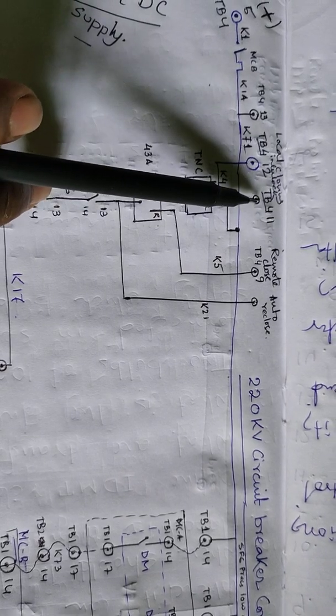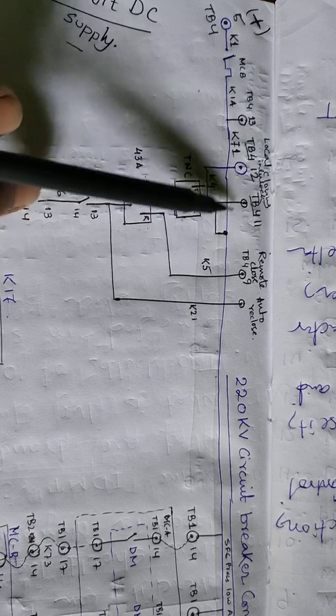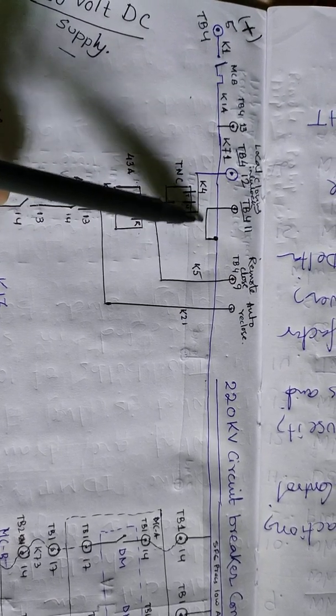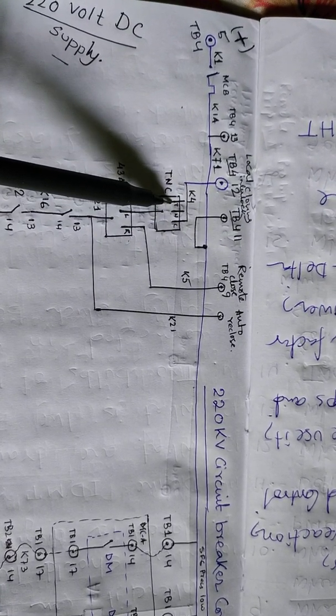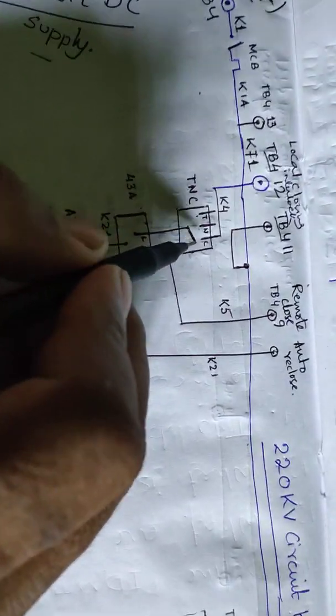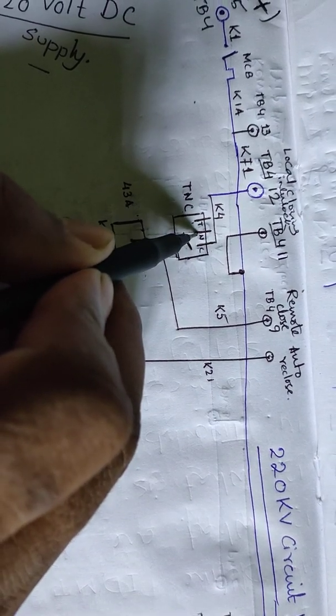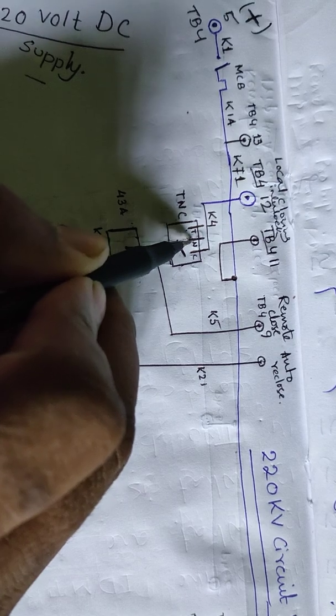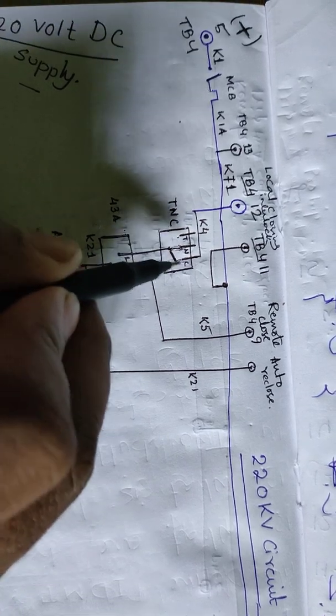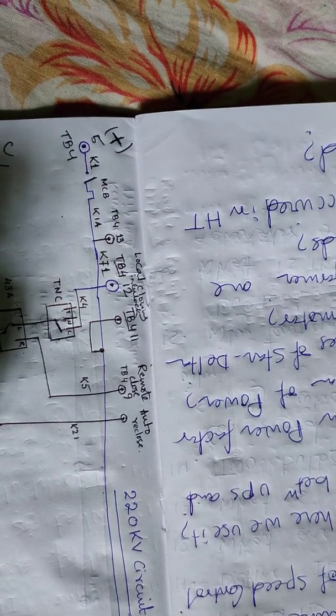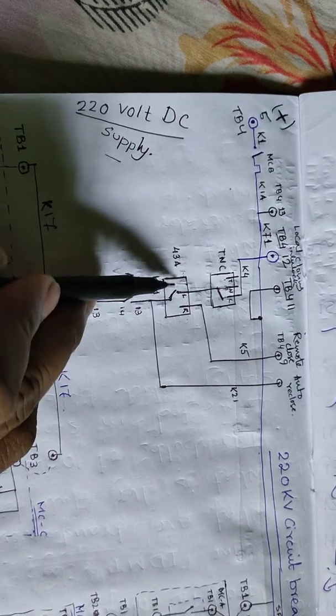This is the local close path, where the DC supply is coming from here and this DC supply is connected to this point. The supply goes through from this point to this point, and the DC supply is at the close terminal. If we want to close this circuit breaker, we have to turn the pistol grip mechanism TNC switch to the close position, and then the DC will be through.